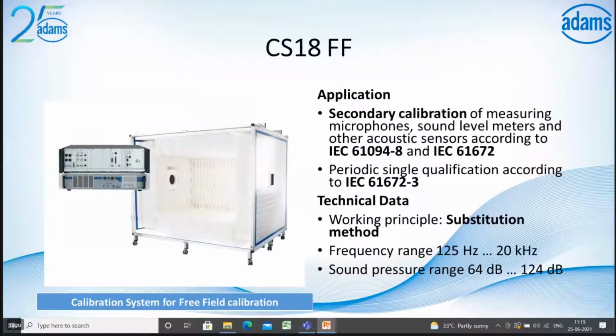CS18FF, that's the free field calibration. It's a secondary calibration according to the standards IEC 61094 for working standard microphones and IEC 61672 for sound level meters. And this works based on the substitution method, where the master microphone is calibrated initially and the DUT is placed after that. Based on the substitution, the sensitivity is calculated for the frequency range 125 Hz to 20 kHz, and the maximum sound pressure you can go up to is 124 dB.